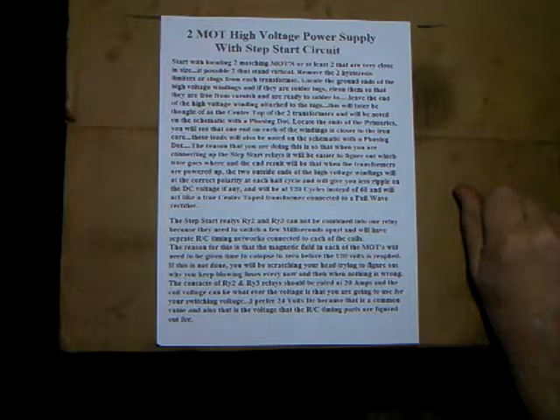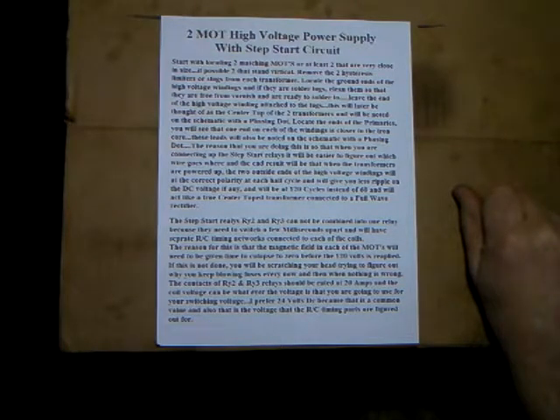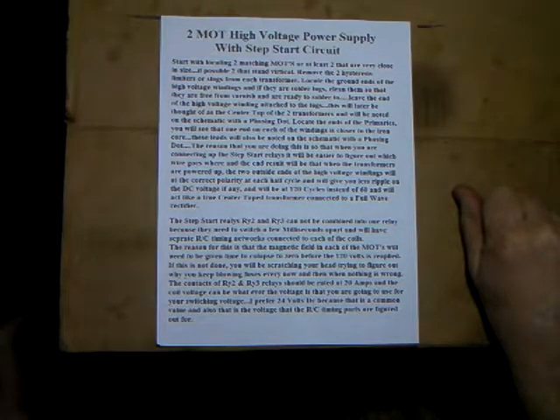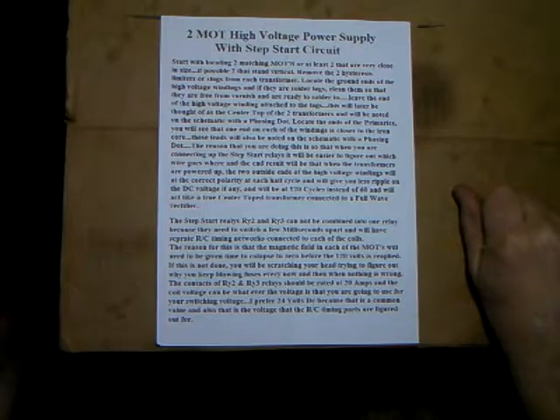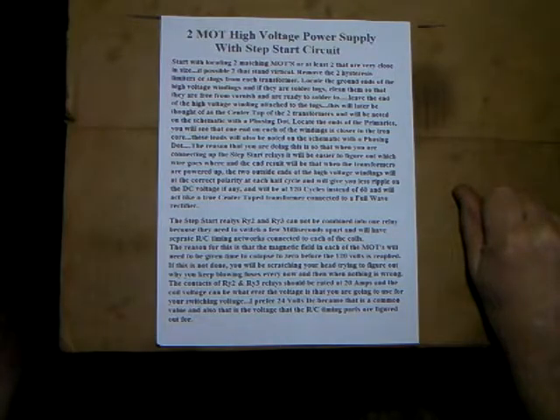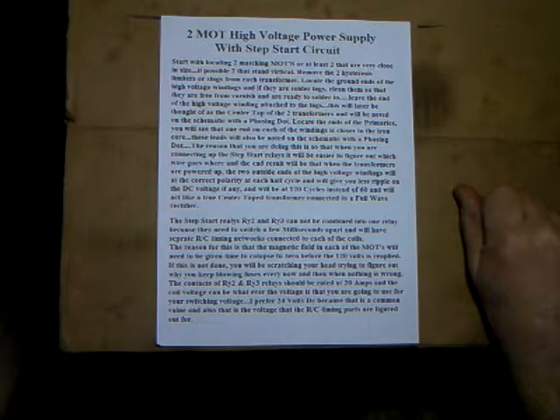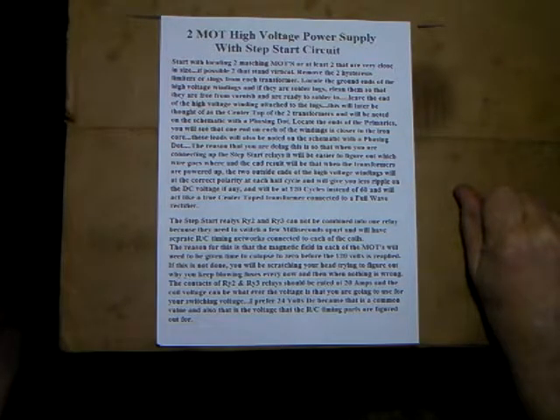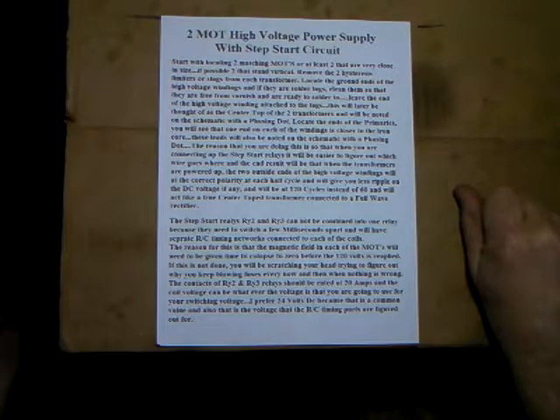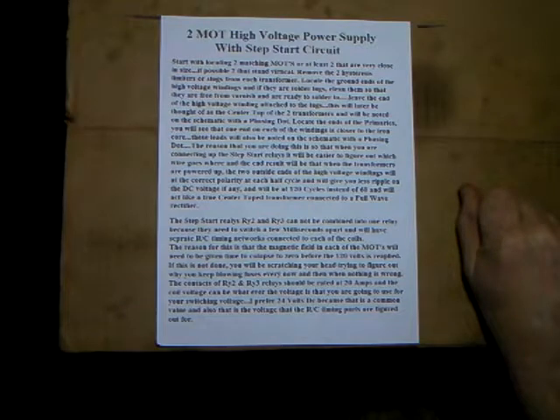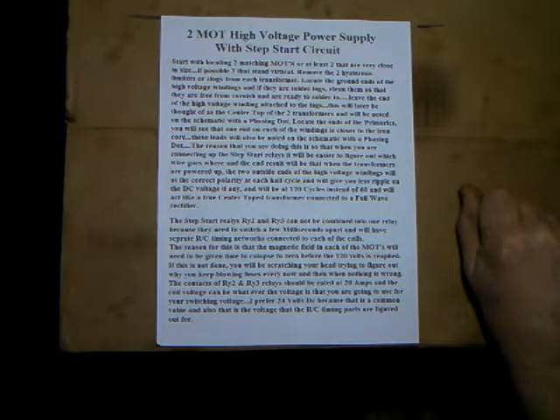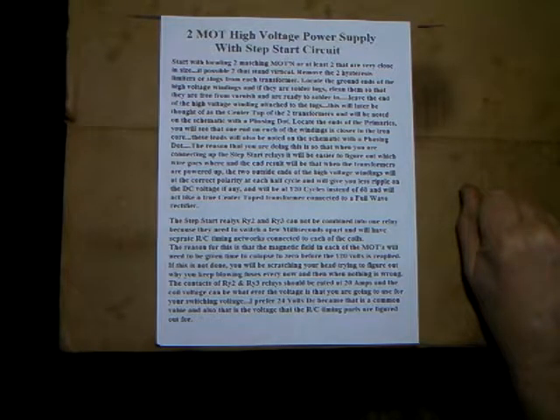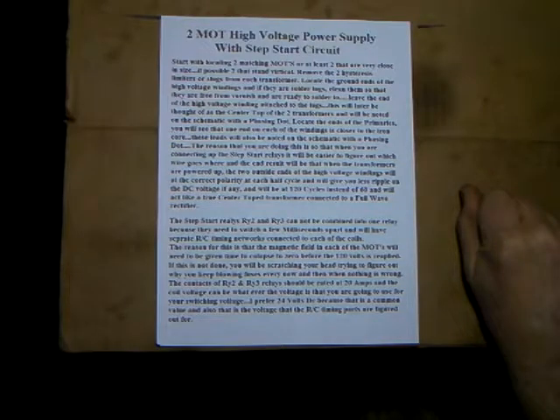Okay, locate the ends of the primaries and you'll see that one end of each of the windings is closer to the iron core. These leads will also be noted in the schematic with a phasing dot. The reason you're doing this is so that when you are connecting up the step start relays it will be easier to figure out which wire goes where and the end result will be that when the transformers are powered up the two outside ends of the high voltage windings will be the correct polarity at each half cycle.